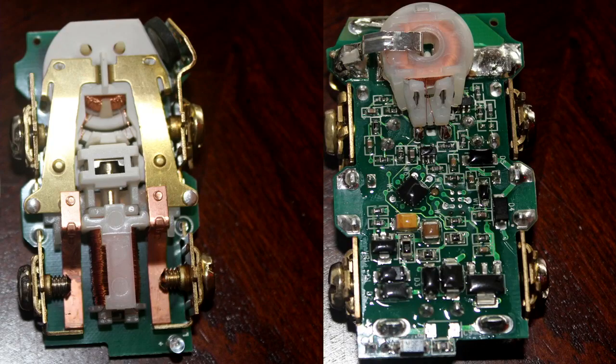Okay, Michael. Well, we're looking at the inside of that AFCI breaker, and I'm not seeing an MOV. How are the arc fault devices doing with the line surges? I mean, we know we have trouble with GFIs. We saw that picture when we covered the GFCIs, and the MOVs. And the question is, how are the electronics being protected from the transients? I don't see the MOVs here. And I need to get with the manufacturers and ask them, show me the picture in a receptacle.